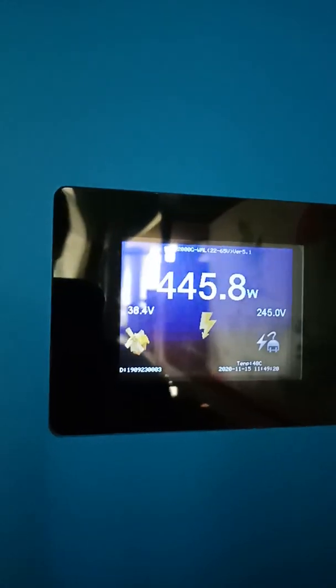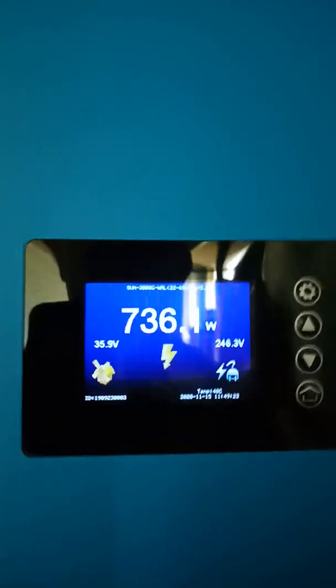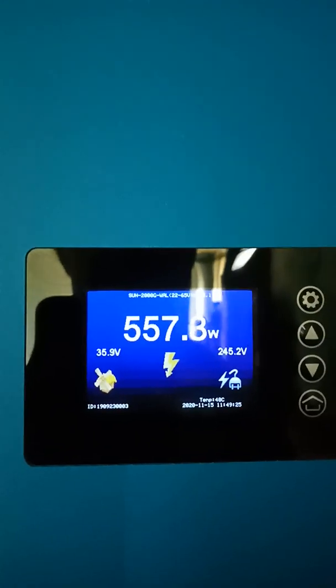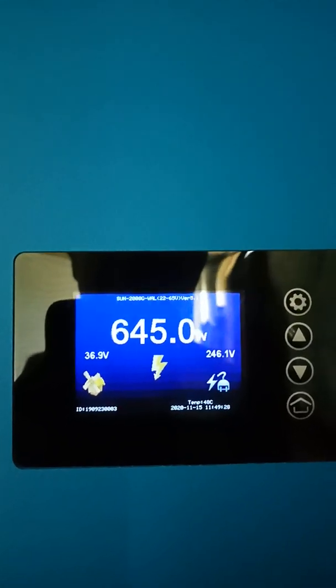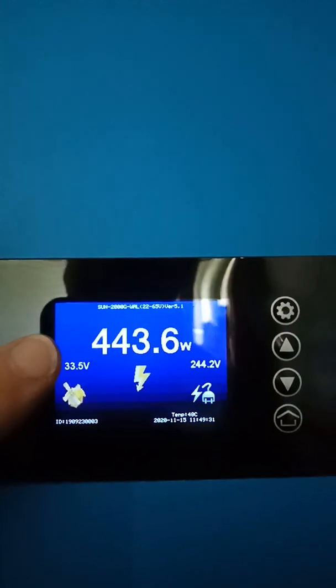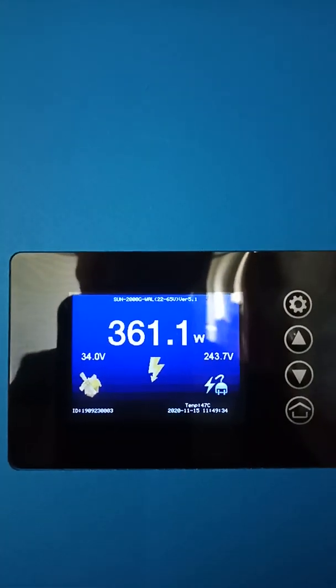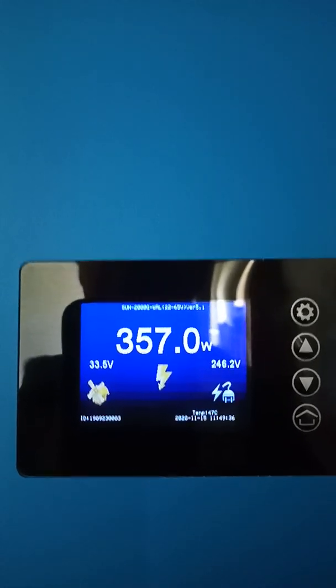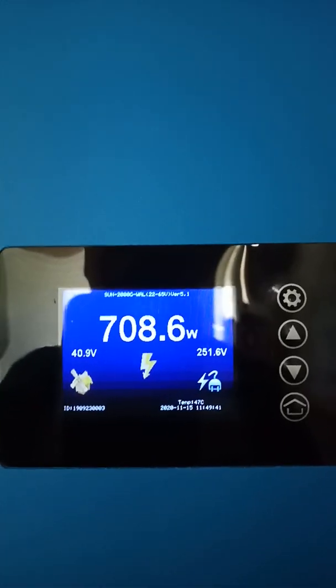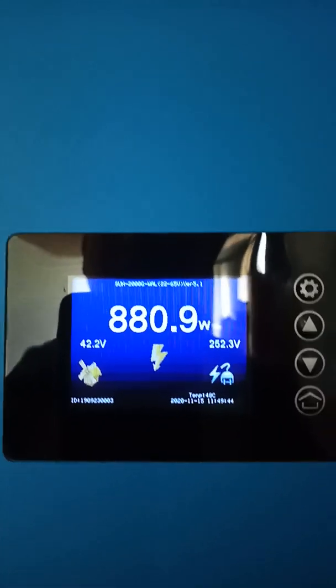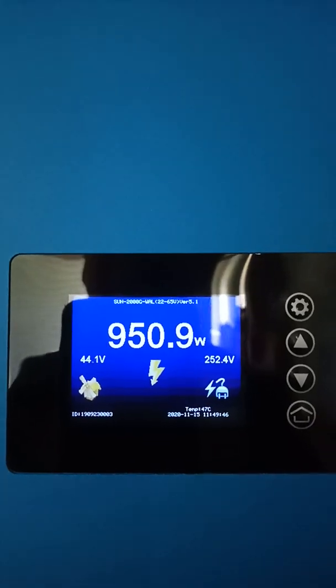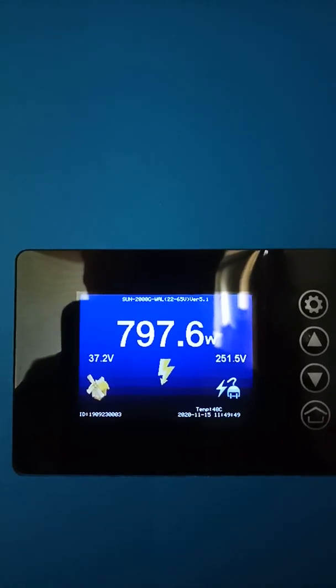Here we've got a big wind gust going through this unit. We can see the voltage on this side, it's keeping it down. It's a 20 volt turbine, so I'm trying to keep it as close as possible to 20 volts really. When it's 40, that's when this gets a lot of load and the inverter has to be struggling a bit to try and keep up with it.